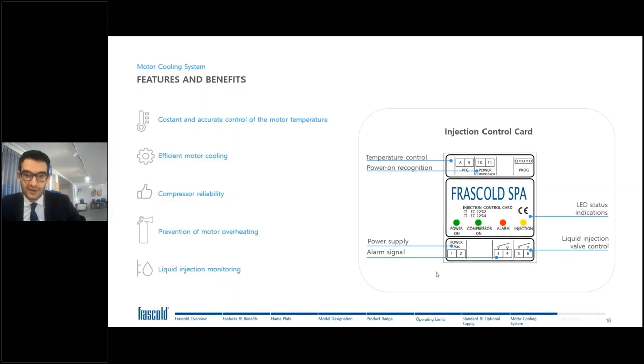Okay, let's see very in detail the injection control card. What is the function of this device? This device checks the motor temperature and decides, depending on the motor temperature, if the motor itself needs an injection of fresh refrigerant or not.